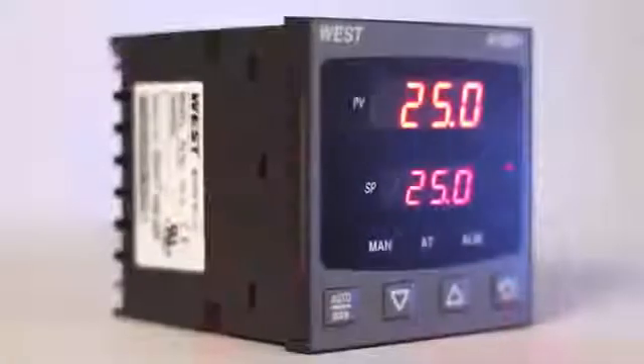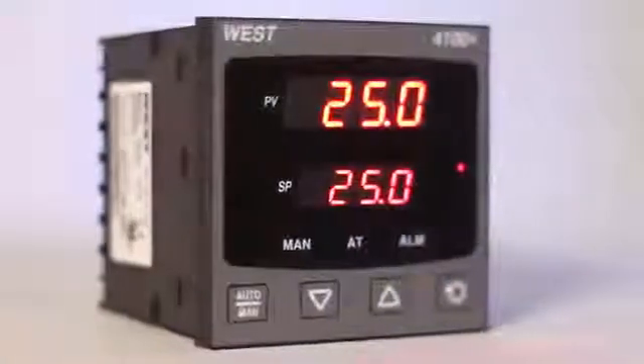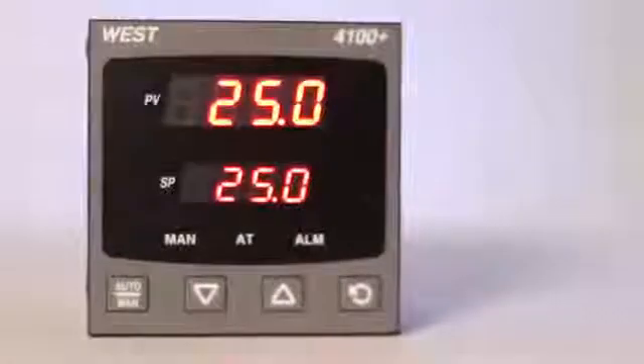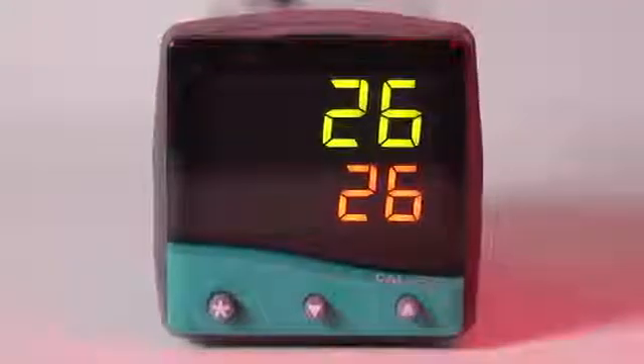Some of the instruments in our range feature a very wide selection of alarms and additional features, but there are two basic types available on almost every model. These are the process high and the process low alarm. In the most basic form they are very simple in their operation. A high alarm set at 100 degrees C, for example, would activate as the process passed that point on the way up, and if the temperature was to drop back below it would deactivate again at probably 99.9 degrees C. In our Cal product range this type of alarm is referred to as a full scale alarm. It is available on all instrument types including indicators, controllers, and the more specialist types of controllers such as profilers and limit controllers.